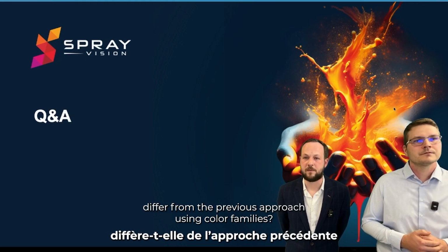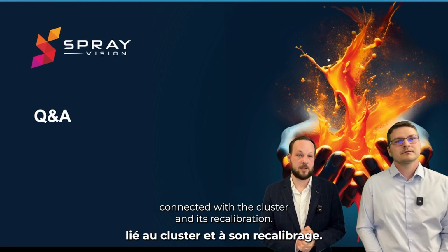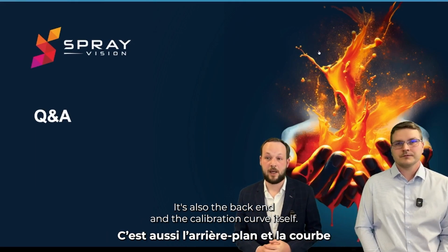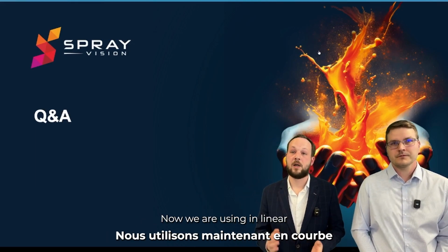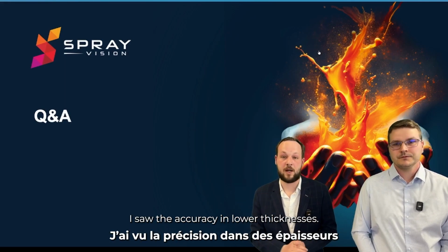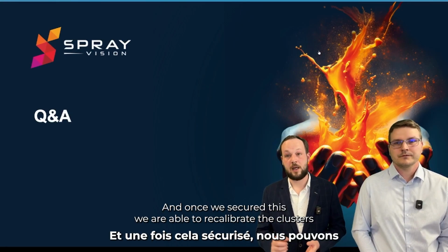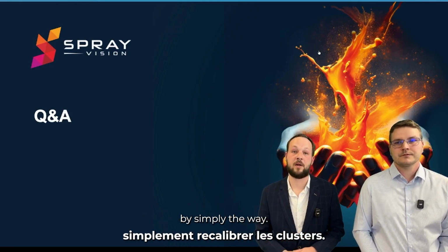And the last question: how does cluster recalibration differ from the previous approach using color families? The calibration of the paint itself is strongly connected with the cluster and its recalibration. As I mentioned, it's not just the front end that we changed, it's also the back end and the calibration curve itself. Now we are using a non-linear curve, not just a linear one, and it will secure the accuracy in lower thicknesses. Once we secured this, we are able to recalibrate the clusters in a simpler way.